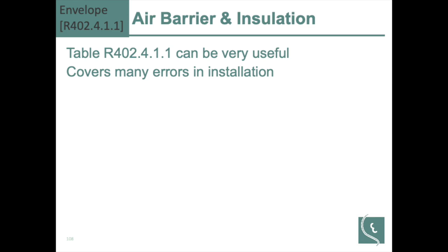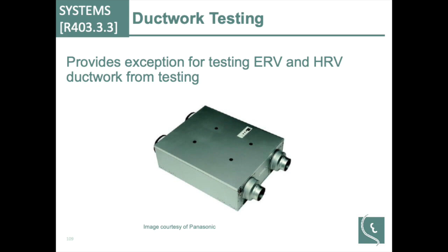Ductwork testing. This provides clarification. If you're using energy recovery ventilators or heat recovery ventilators, that ductwork is exempt from the testing requirements for your pressure test, or for your duct leakage test. If you're doing performance for buildings, there are now allowances for ducts that are fully buried in the insulation, and the code provides guidance as to the criteria to meet this definition of buried ducts, as far as where the R-value is and how much you need to have.